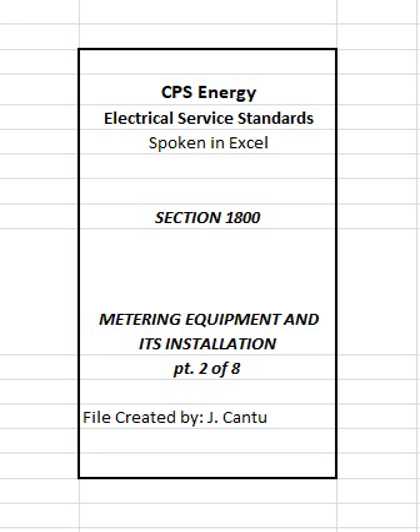Where aluminum service conductors are used, customer shall furnish compression-type connectors with compression tool for installation. Where copper service conductors are used, customer shall furnish heavy-duty pre-insulated connectors. The customer will install the connectors on their service conductors, and CPS Energy will make the connection to the CPS Energy service cables. This junction then will be the POD.